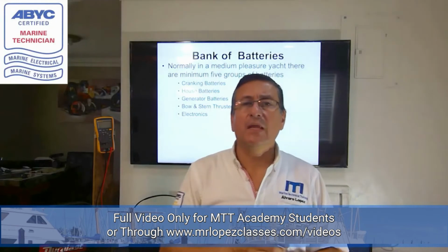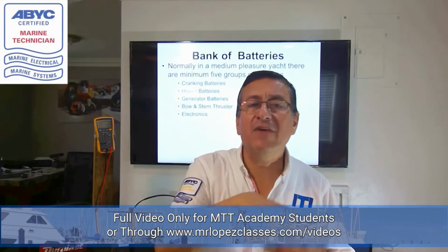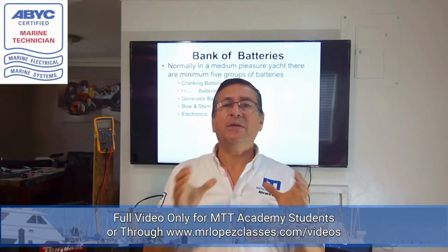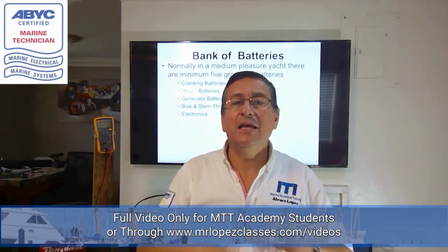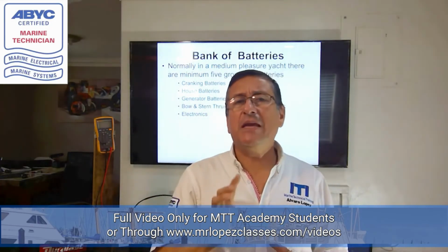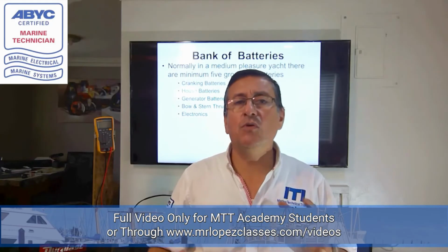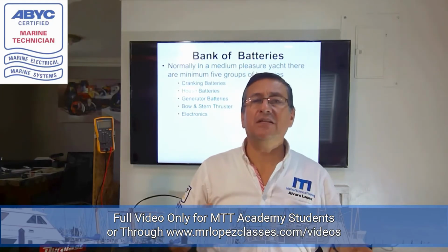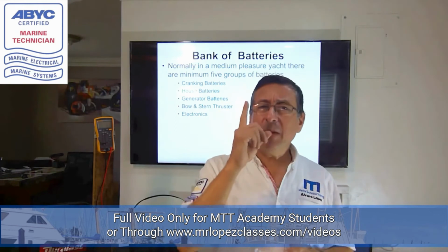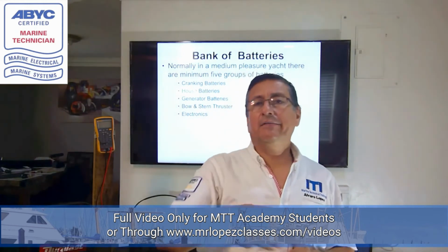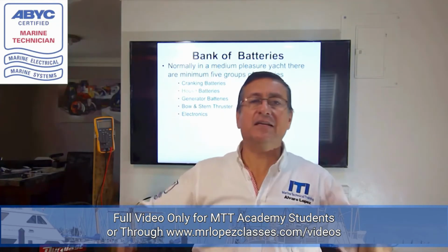Other important thing, if one group of batteries has a problem, in the moment that you check the batteries, I am going to explain right now the procedure to check the batteries. If you found that one battery in the group is damaged, what is the recommendation? The ABYC recommendation is to replace completely all the batteries in that group. Because if one battery is damaged, it's because the other batteries in a couple of days will be damaged. You need to replace the batteries completely, the group. If you replace only one battery, in a couple of weeks you damage all the batteries again.